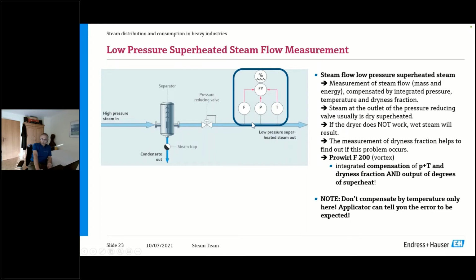That's why you should always compensate by both pressure and temperature. In reality, however, many customers are compensating by temperature only because it's cheaper. But that leads to completely wrong measurements. You can easily have errors of 40% or even 100%, typically over-readings, because you take that temperature reading of your superheated steam and assume this is your saturation temperature. But this results in completely wrong densities, energies, and so on. Don't do that. Compensate in such a layout always by pressure and temperature.